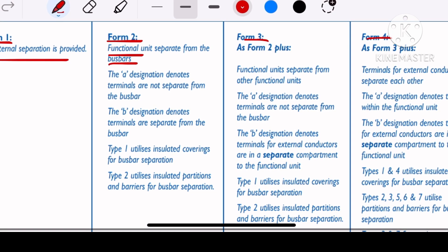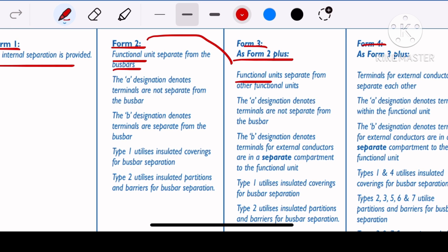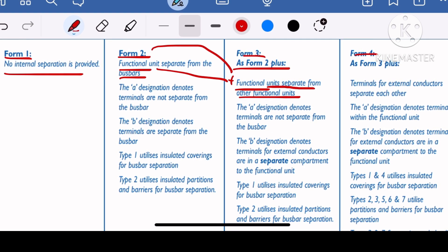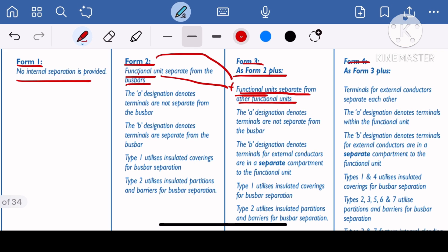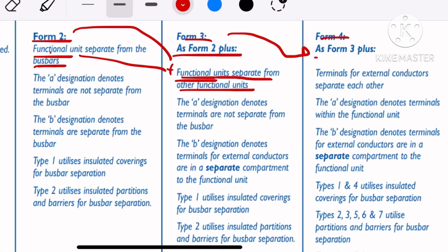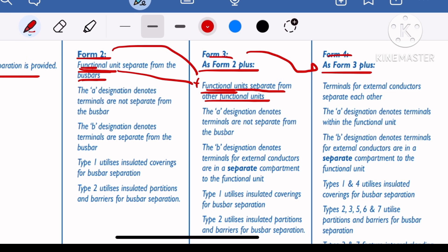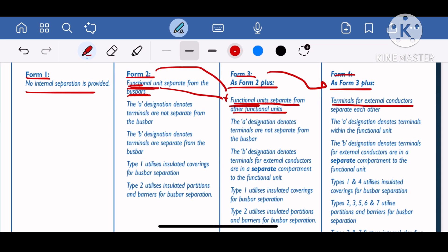In form 3, it builds on form 2, so there will be a separation between the functional unit and the bus bar, and additionally there will be a separation between functional unit and functional unit. In form 4, as an add-on to form 3, there will be separation between bus bar and functional unit, separation between functional unit to functional unit, and additionally the terminals for external cable conductors are separated from each other.